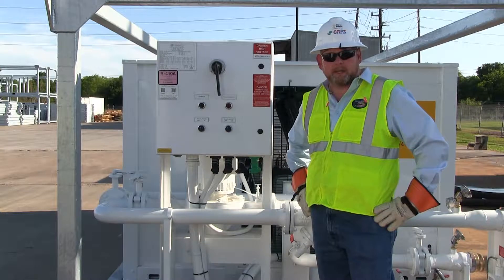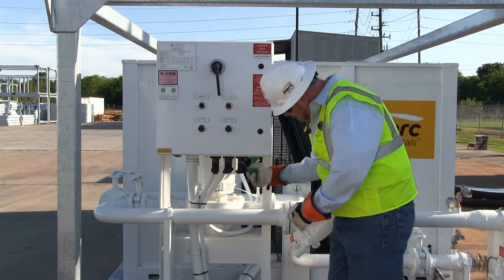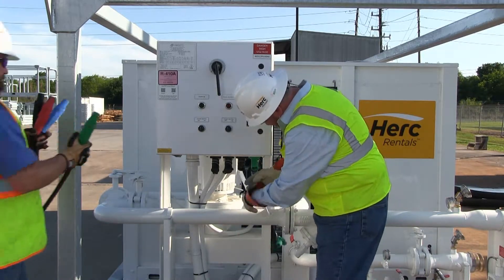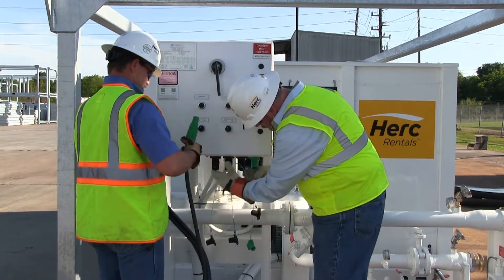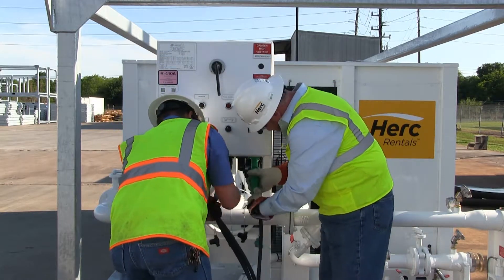The next step in our setup is to connect the main high-voltage 480-volt camlock cables. We're going to do that by removing the protective camlock caps from L1, 2, and 3 and the ground. Remember to always hook up the ground first.